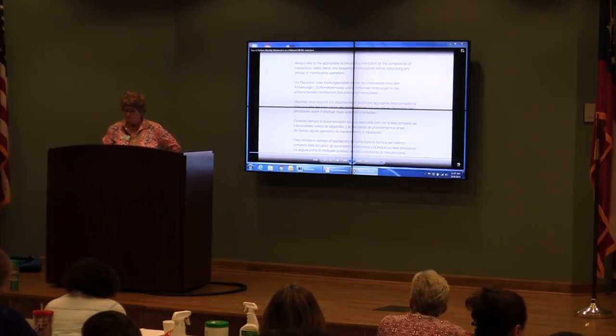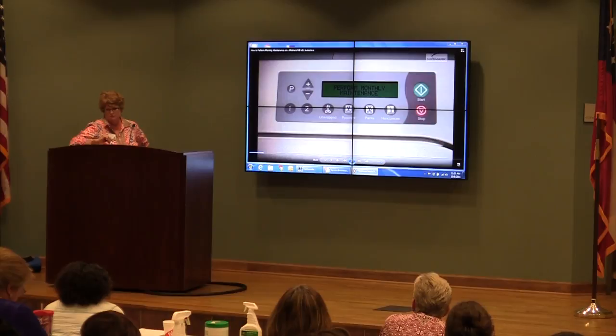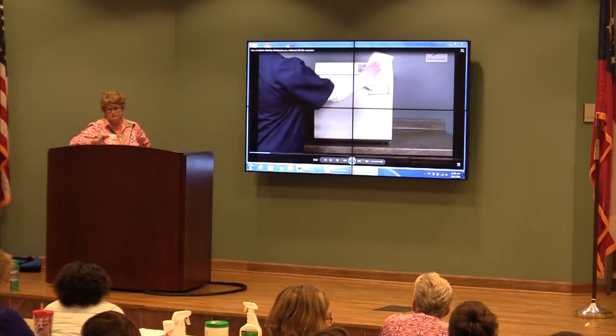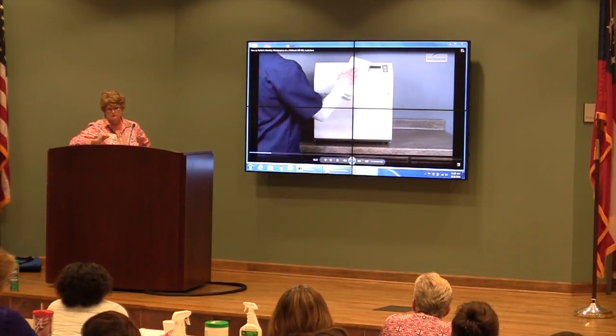However, always refer to the appropriate technical documentation for the complete list of instructions, safety alerts, and sequence of procedures before conducting any service or maintenance operations. Every 28 days, the autoclave will automatically display the Perform Monthly Maintenance message. This is a more thorough cleaning of the unit and involves multiple steps.